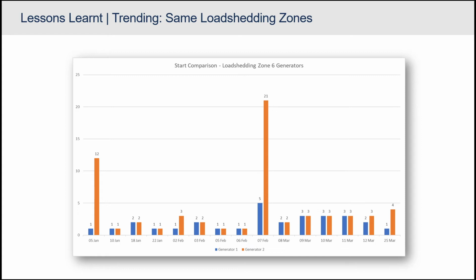Ignore the 7th of February. On the 12th and 25th of March we had a very similar situation. What we found was a fuel line issue that had become normalized. The guys on that site were so used to having to start that generator more than once to get it going before load shedding that they never reported it.